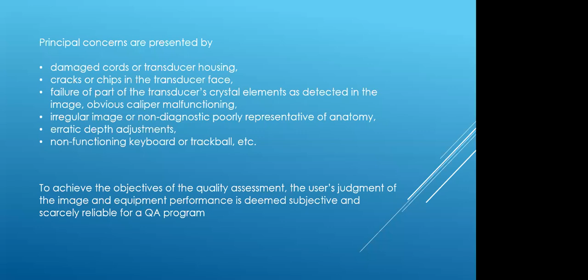Right. So now we are saying you could set up your QA system in a way that fits within your budget. You could find basic measurements which do not need specialized equipment, right? For example, just firing the ultrasound into air and looking at the reverberations, where you're looking at different points. As long as they are consistent, then you are fine. But you could also use phantoms, right? Phantoms are good because they give you a determined measurement environment where, for example, if you're going to measure distances, you know exactly what the distance is because it's fixed. Or if you're going to measure elasticity, you know because the material in the phantom is known.